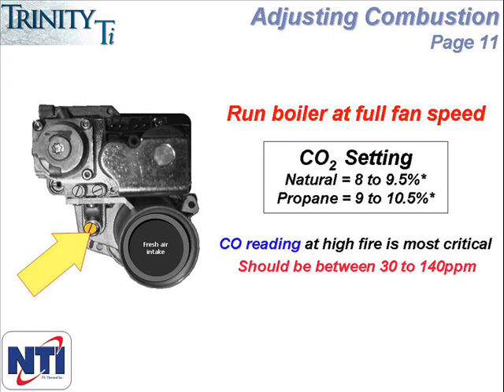Setting the CO2 should be done with the boiler running at high fire, which is a gas input value of 240. Perform a combustion analysis at high fire and read the CO2 level. Ideally you want the CO2 reading to be 9% when using natural gas and 10% for propane. If the reading is already there, no adjustment is necessary.